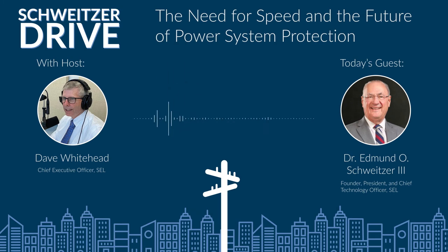And when you start to think about it, if the energy is moving at the speed of light, and we're going 6 microseconds a mile, it doesn't make a lot of sense to me for the protection, the relay and the circuit breaker, to sit around waiting for 20 or 30 milliseconds to get going. And sometimes it's even worse than that when we use time coordination, which should be relegated to backup protection only, where the fault tripping times get into the seconds. So we need to think in milliseconds, microseconds, nanoseconds today.